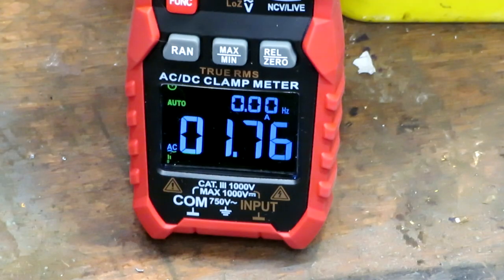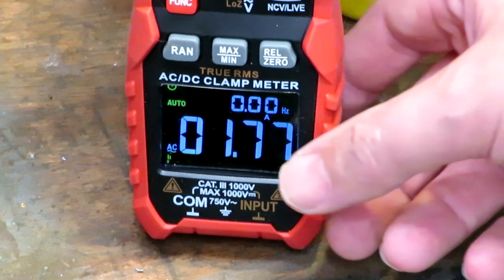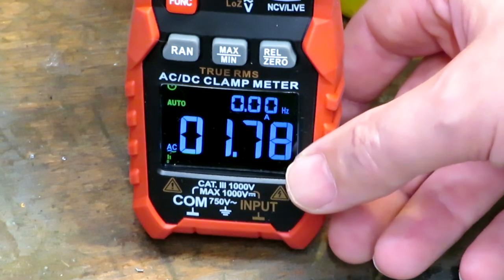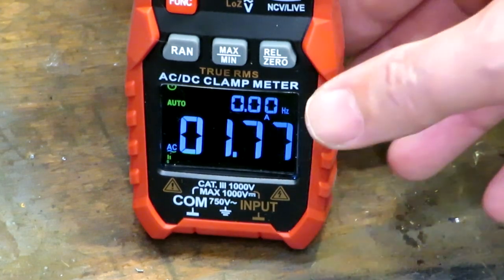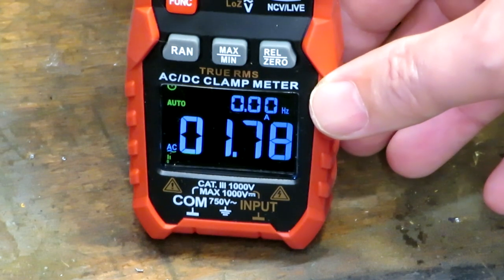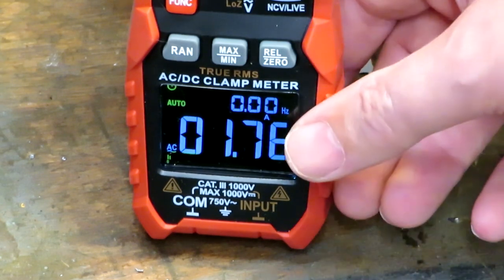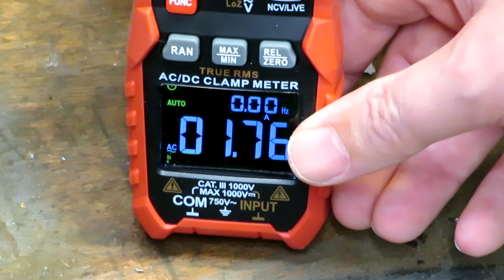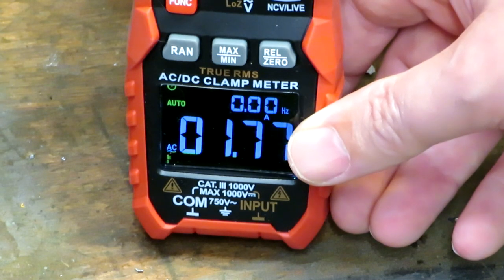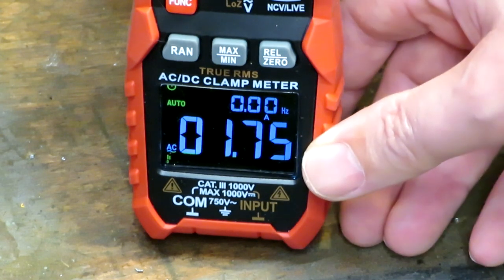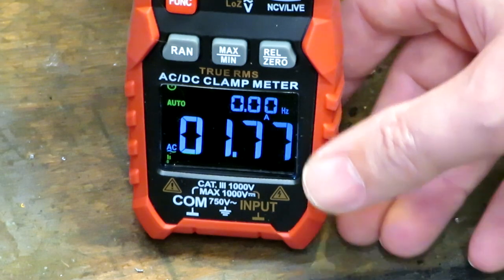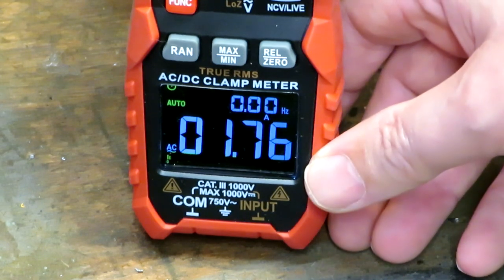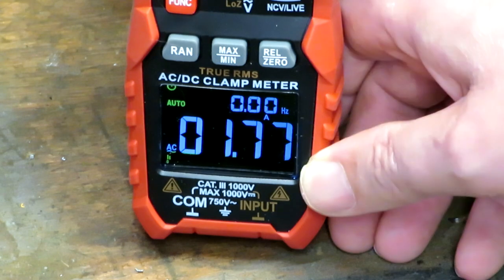We can see with our transformer switched on and without any tools actually connected to it, our transformer is still drawing 1.78 amps of current from the mains, so this transformer would actually appear to be quite a high loss transformer. So we're actually putting 1.78 amps into this transformer and we're getting no useful work out of it, so all that is effectively its loss, so it's all inefficiency. And if you've watched some of my previous videos, you'll actually know that these losses are iron losses within the transformer itself. But let's have a go now at measuring the actual inrush current to the transformer.